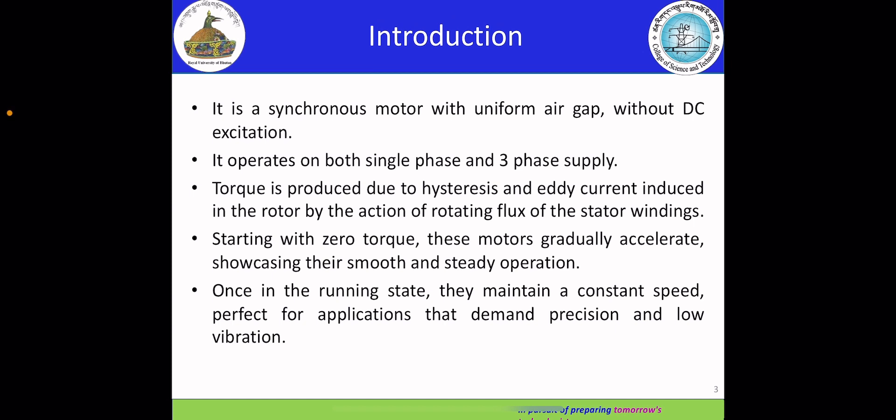Firstly, I am going to give a brief introduction on the hysteresis motor. It is a synchronous motor with a uniform air gap without DC excitation. It operates both on single-phase and three-phase supply. Torque is produced due to hysteresis and eddy current induced in the rotor by the action of the rotating flux of the stator windings.